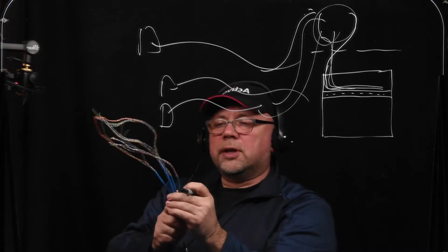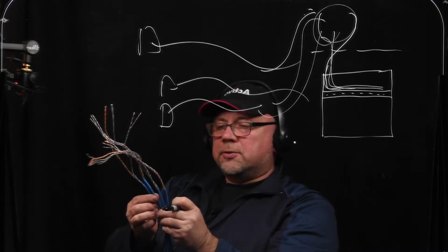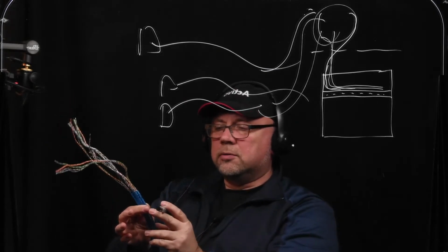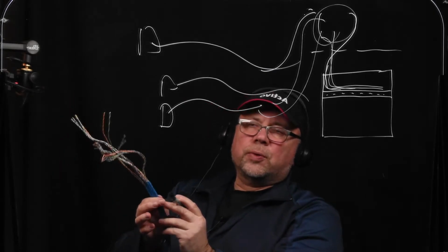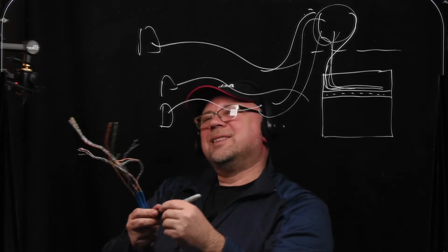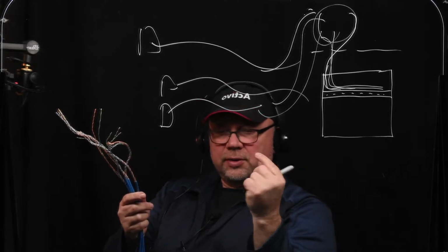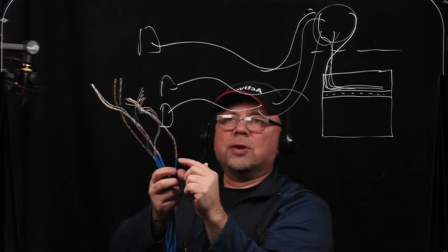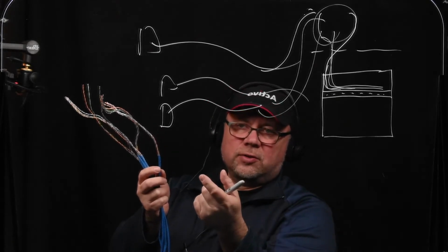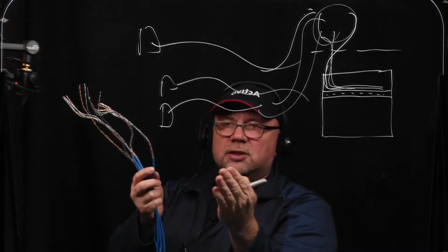Now, I'm showing you this, and I can see some people on YouTube or the internet are going to start screaming at me, "Oh, you're using the Sharpie to label, we don't do that anymore." Yeah, sometimes we do, okay? But yes, if you want to do it properly in the industrial way, there are label printers that print what's called a wraparound label, and you can print the whole designation of the wire according to the instructions that you're given, and just wrap it around and stick it on. Yes, that's the proper way of doing it.